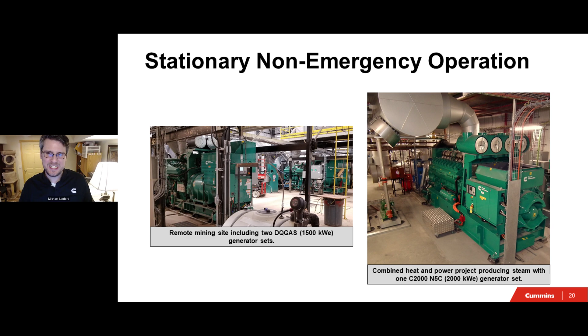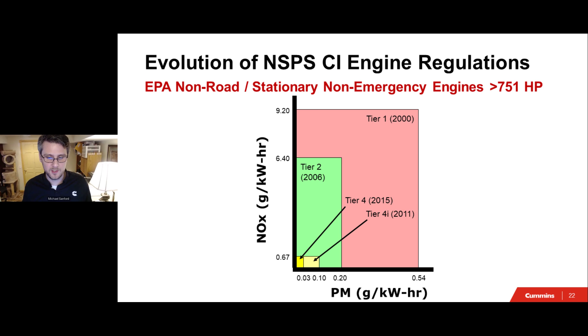The expectations for emissions are much different. The types of applications that are most commonly associated with non-emergency are things like demand response, peak shaving, rate curtailment, interruptible. A lot of these words are used somewhat interchangeably. My recommendation to you is if you see any of these words, you're talking with a customer, an owner, an operator, end user, an AHJ inspector, someone who's talking about these things, you need to be thinking about the non-emergency certified product, typically what we consider a tier 4 product for diesel recips today.